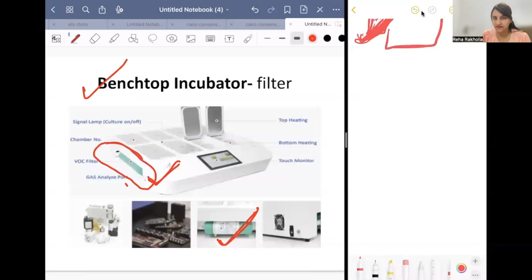Right now I'll show you the diagram. Important condition: these carbon filters are effective only when the atmosphere is not humidified. Water on the surface of the carbon filter reduces its ability to remove VOCs. See, this is the intra-incubator filter for the big box incubator. It is kept inside the big box incubator. Now this is the benchtop filter, and it can be seen in both the time-lapse and benchtop incubators. So there is actually double filtration: the inline filter and the intra-incubator filter.